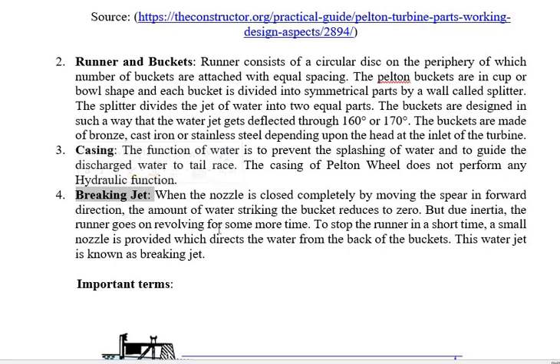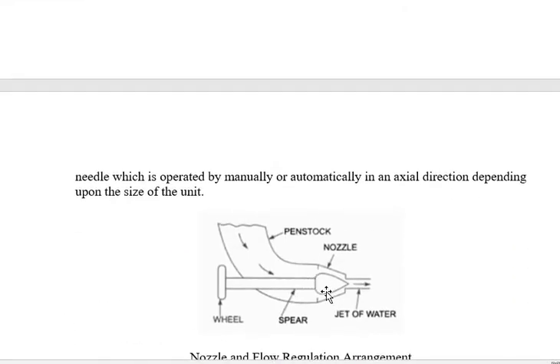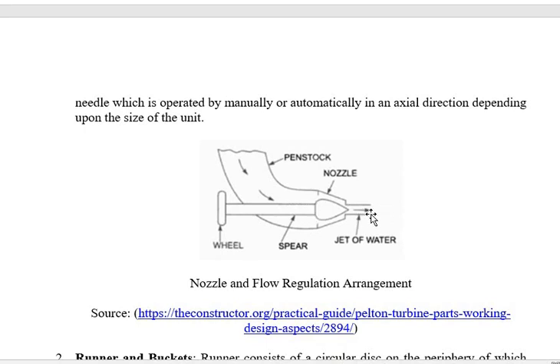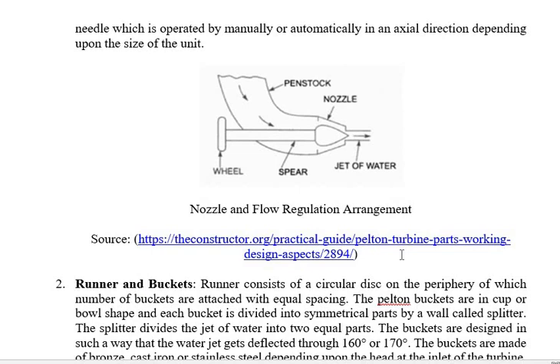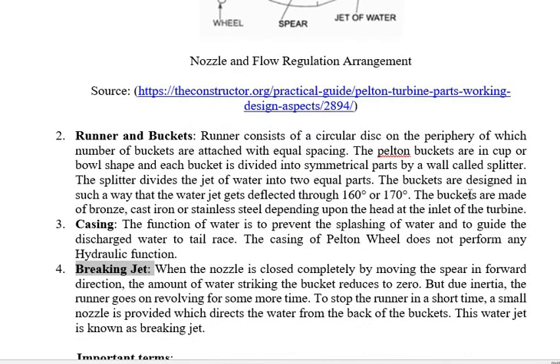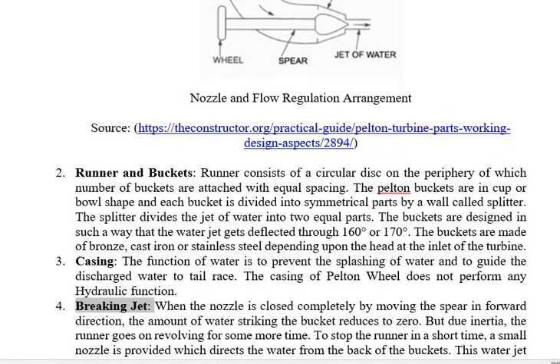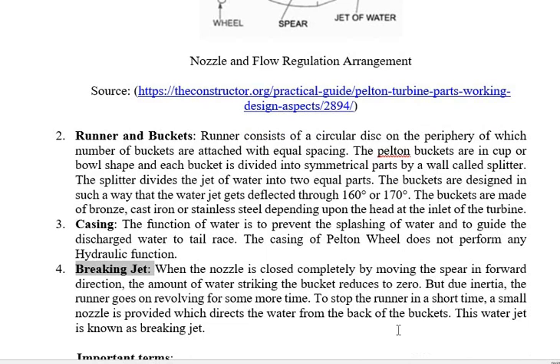Another important part is the braking jet. When the nozzle is fully closed by moving the spear forward, no fluid strikes the wheel. However, due to inertia the wheel will still continue rotating, causing a loss of energy. To stop the wheel quickly, a braking jet is placed opposite to the main nozzle — it is also supplied by a small nozzle.